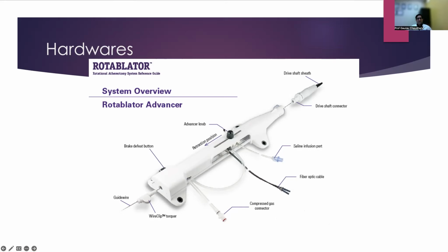So this is the advancer knob. It moves forward and backward. Once we move the burr inside, it moves forward, and if we move it back, it moves backward. Once we are taking the burr, we rotate this and lock it at the 2/3 and 1/3 junction, leaving the two-finger breadth behind. Because once we are inside, many times we need to remove the tension, and for that we have to remove the lock, move it forward and backward, and also press the Dynaglide button to remove the tension in the rotor wire.